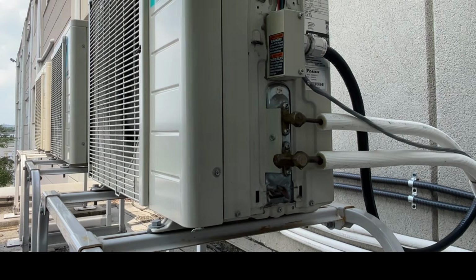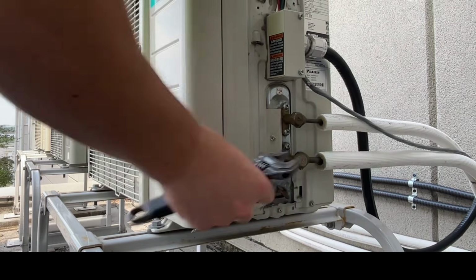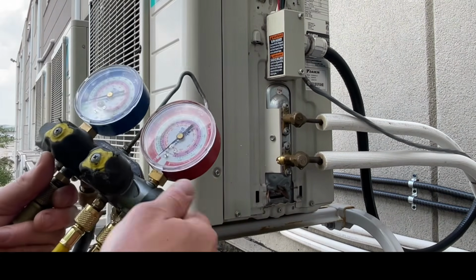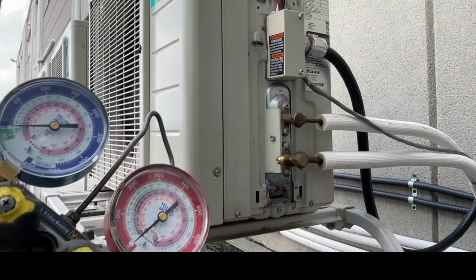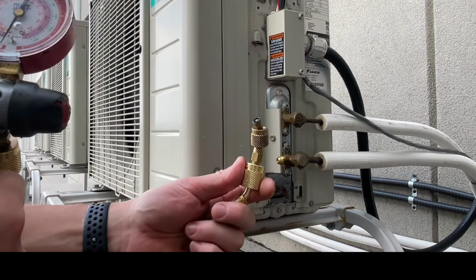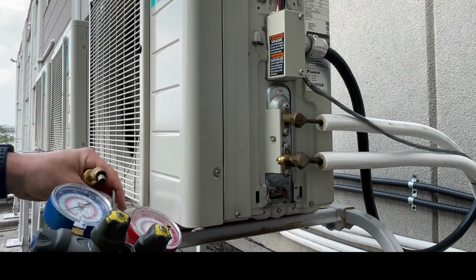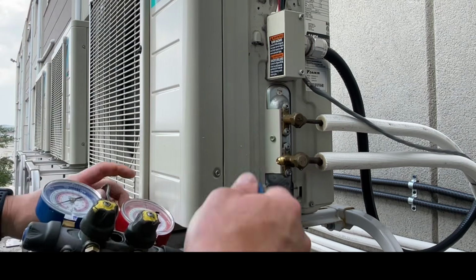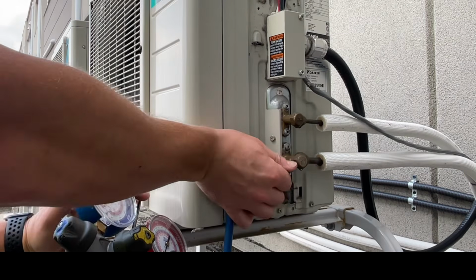All right, now we'll check our running pressures. We're gonna go through this service fitting right here. Unfortunately, on these units, pretty much all ductless split units, they don't use the standard 1/4-inch connection, which is how your manifold gauges usually come. You have to buy this stupid adapter, which is 5/16. But anyways, let's throw these on. We'll double check our pressures, and that'll probably be a wrap. Maybe I'll show you guys how to navigate the app a little bit more after.